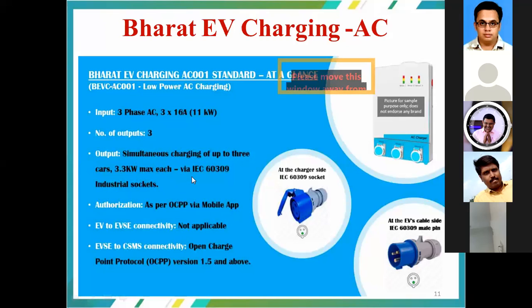And again, the standard for the socket is IEC 60309, as we already discussed. And the structure of the IEC 60309 socket is as shown. Again, it is going to have 3 terminals or 3 lines, wherein we are going to draw the power from all the 3 lines simultaneously. And next comes the EVSE to CMS connectivity, that is Open Charge Point Protocol, abbreviated as OCPP, and the version is 1.5 or above. So these are all the sample connectors available at the charging stations as far as the Indian standard is concerned.